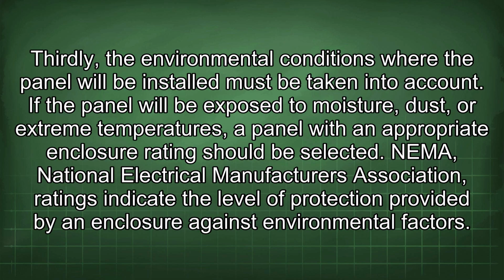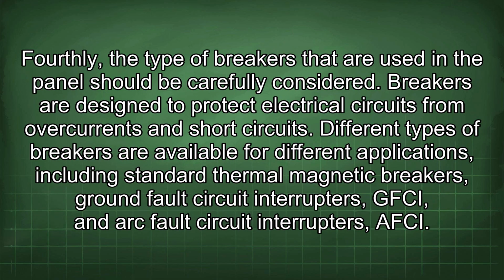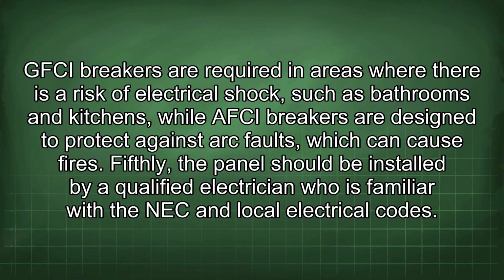Thirdly, the environmental conditions where the panel will be installed must be taken into account. If the panel will be exposed to moisture, dust, or extreme temperatures, a panel with an appropriate enclosure rating should be selected. NEMA, National Electrical Manufacturers Association, ratings indicate the level of protection provided by an enclosure against environmental factors. Fourthly, the type of breakers that are used in the panel should be carefully considered. Breakers are designed to protect electrical circuits from overcurrents and short circuits. Different types of breakers are available for different applications, including standard thermal-magnetic breakers, ground fault circuit interrupters (GFCI), and arc fault circuit interrupters (AFCI). GFCI breakers are required in areas where there is a risk of electrical shock, such as bathrooms and kitchens, while AFCI breakers are designed to protect against arc faults, which can cause fires.